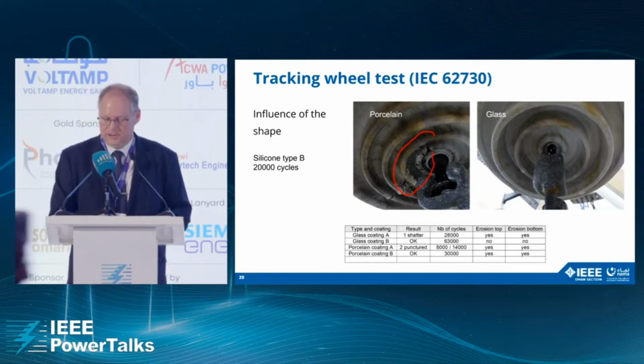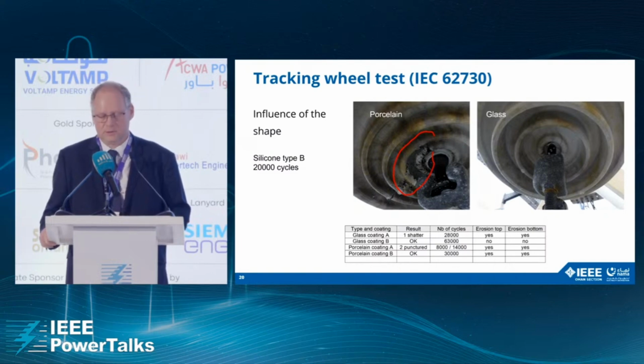So even if this test is not used at this point in any standard for silicone coating insulators, the outcome should be considered with interest. The test is relatively rapid and not too complex to put in place, and it appears to provide the following elements. Ability to survive strong electric activity can be discriminated. A ranking of coatings performance can be established, and adherence recovery can be demonstrated in this test.